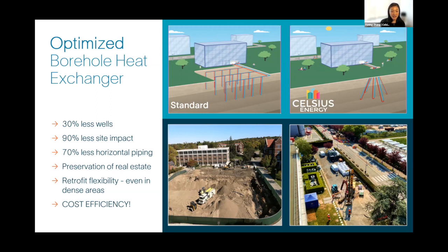Because of this, we're also reducing the amount of plastic that goes into the installation since we no longer need all those horizontal pipes that connect the vertical boreholes together and lead into the building. That also reduces the amount of water necessary for drilling, and reduces the total number of holes that need to be drilled. All of this together reduces your total installation cost, which is a huge factor.